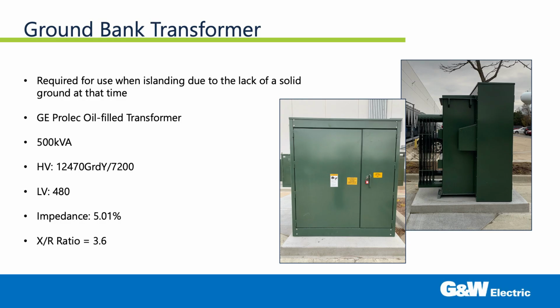And the last piece of hardware is our ground bank transformer. The reason we need a ground bank transformer is when we isolate from ComEd, we no longer have a solidly grounded system, so we needed something to have that ground in there. Working with Quanta, we developed the size of the ground bank transformer we needed.